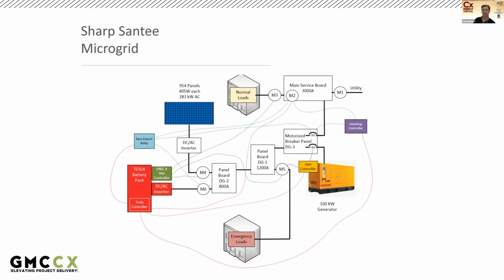So I will move on to this slide, just going back to the diagram. I'm not really going to dive into exactly what the wiring is, but here's an example of how the communications controls for the microgrid are decentralized. This means the intelligence for the system is distributed. There's no one central brain. Like I said before, there's the non-export relay, the Enel X site controller, a Tesla controller, a generator controller, and the islanding controller. So there are many different controlling components that need to work together safely and efficiently. That's where we as commissioning agents can come in and help make sure we test through all these scenarios, because there are so many different pieces and parts to make sure it operates smoothly.